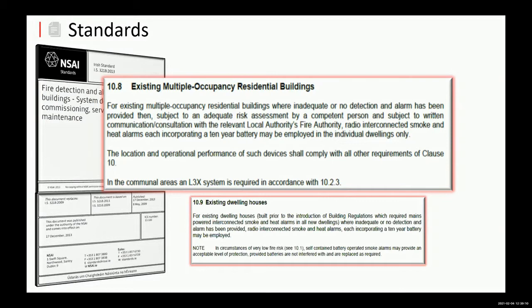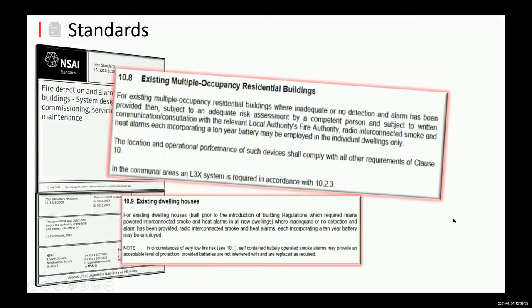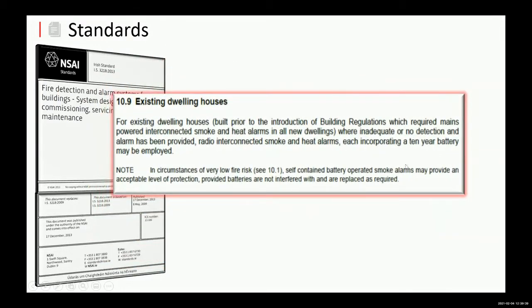Where buildings have inadequate or no detection, an alarm system or alarms are provided subject to adequate risk assessment by a competent person and subject to written communication with the local fire authority. Radio interconnected smoke and heat alarms, each incorporating a 10-year battery, may be employed in the individual dwellings only. Okay, so that's allowed, and that is a very big part of the business that we're doing at the minute in relation to upgrading of apartment blocks that were built back in the day. If you look at existing dwelling houses, what they're saying here in 10.9, anything built prior to the introduction of building regulations where it didn't require mains powered units, they say now the best installation there, if you want to put in just a fire alarm detection system, is the 10-year battery operated radio interconnected smoke and heat alarm.